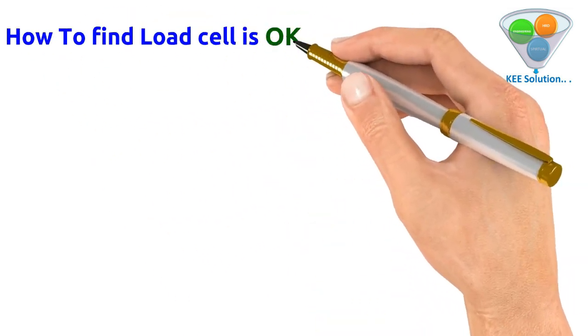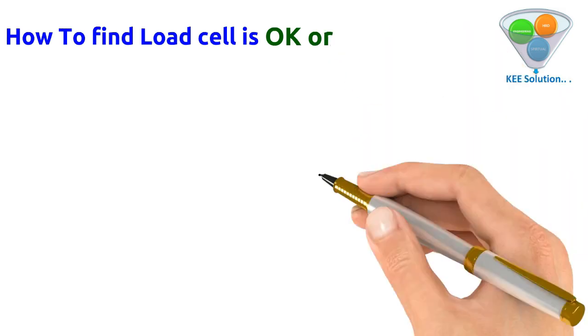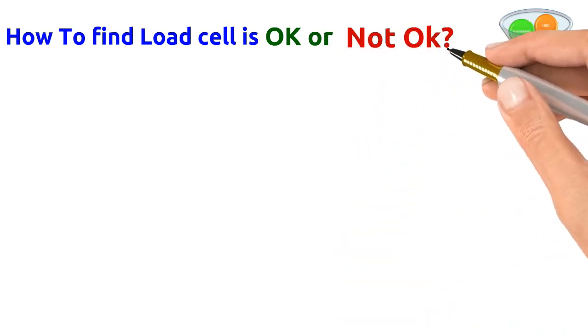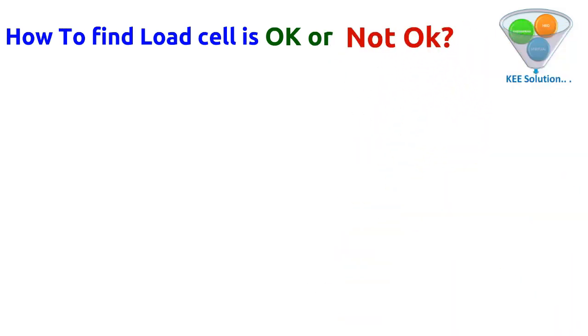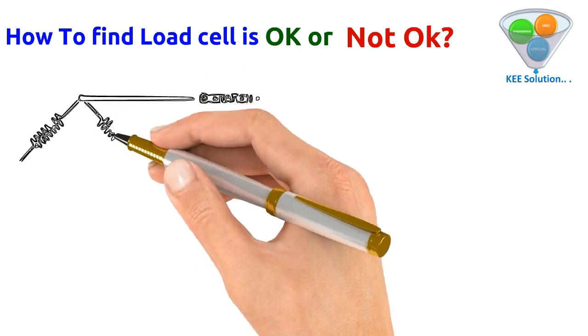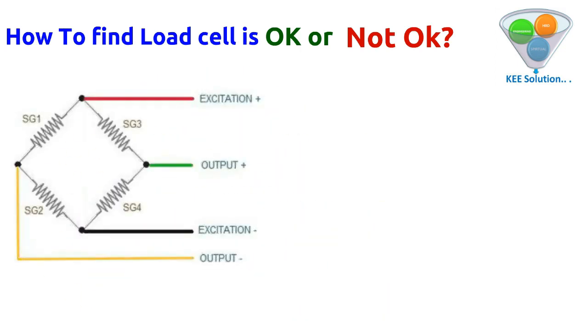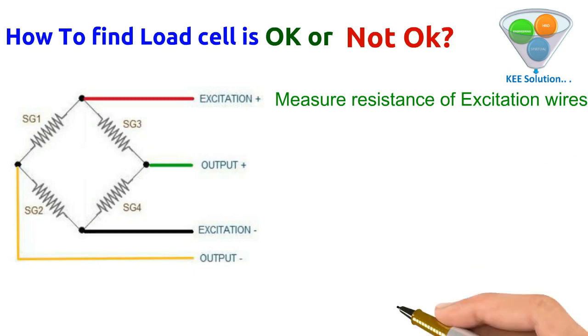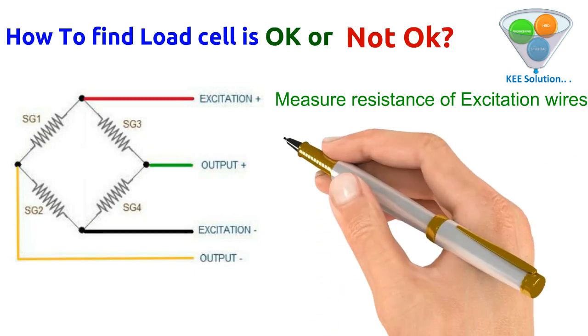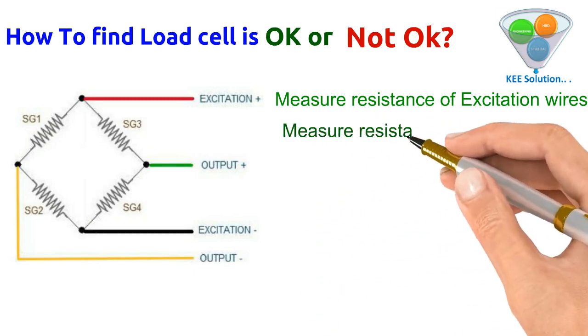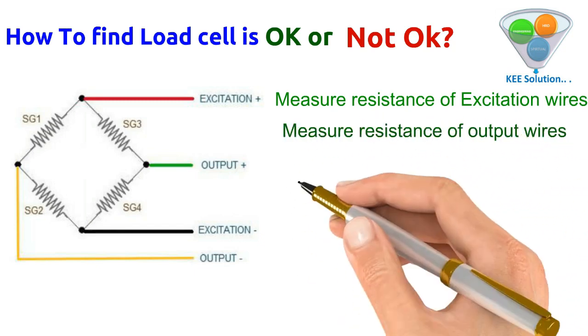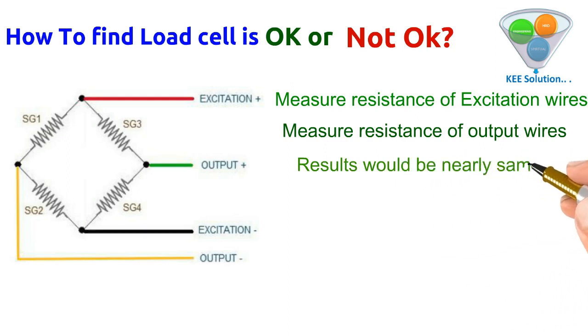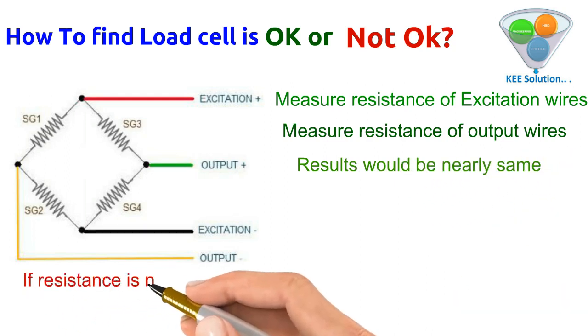Now we will find out how to determine if a load cell is OK or not by measuring its resistance. Measure the resistance between the two excitation wires, then measure the resistance of the signal/output wires. The result should be nearly the same if the load cell is OK.